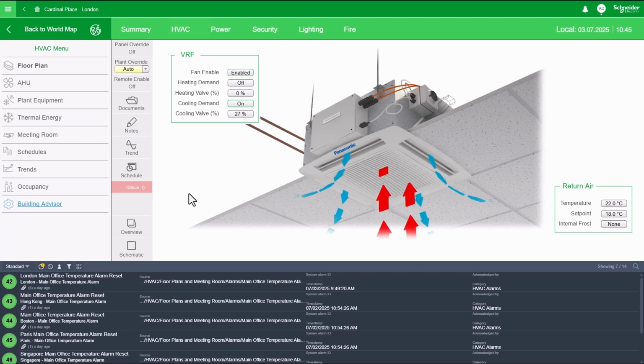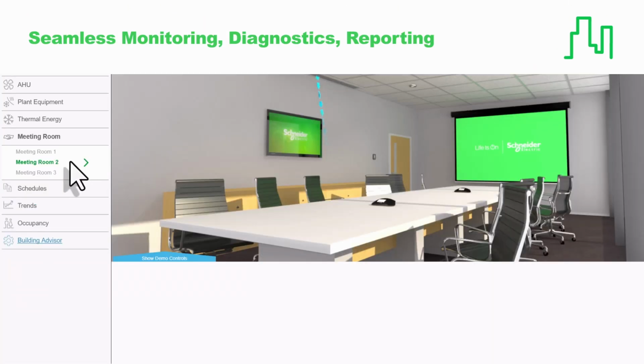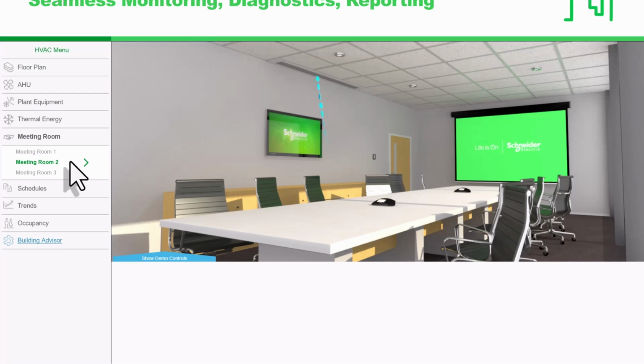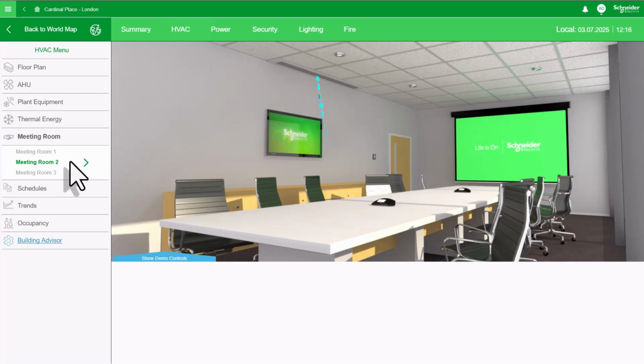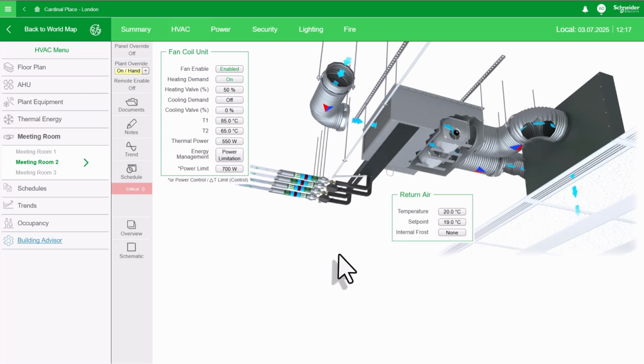While I'm here, I'll also follow up on another ticket related to valve noise in Meeting Room 2. This space is serviced by a fan coil unit, equipped with SpaceLogic SP90 actuators, which drive our pressure-independent control valves. These are high-performance components, and when they were installed, we also added diagnostic screens to help troubleshoot any issues that might arise. I'll click on the ceiling diffuser to bring up the fan coil unit.